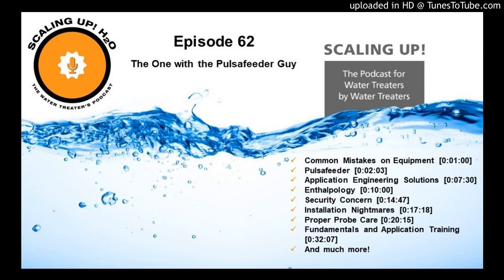Let me ask, what would happen if somebody did put the probes in the wrong orientation? Well, inside the probe is an electrolyte buffer, and proper installation ensures that the buffer and the semi-permeable glass membrane on those probes exchange at an acceptable rate with the process. Mounting the probe incorrectly will typically expedite the electrolyte buffer getting out of the probe, which will kill the probe as well.